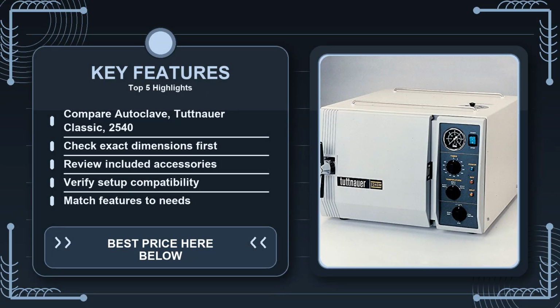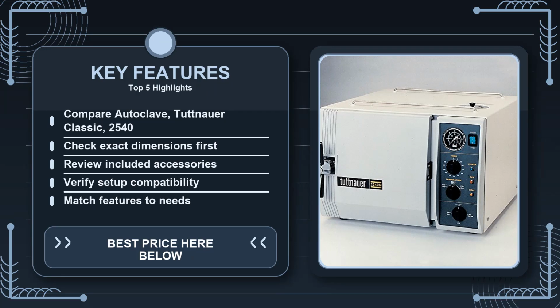Speaking of cycles, the actual time to a full sterilization run on the Classic is around 30 minutes for a standard load. That's not the fastest on the market, but it's consistent. If you're used to instant sterilizers that claim 10-minute cycles, keep in mind those often cut corners on temperature verification or only work for very small loads. The Classic's 30-minute cycle hits the 121C, 250F mark for the required hold time, which aligns with most regulatory guidelines for medical devices. In practice, that means you can load a tray, start the cycle, and have it ready before the next patient comes in, assuming you're not pushing more than a couple of loads per hour.